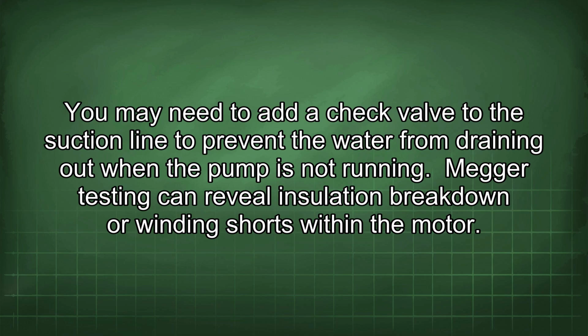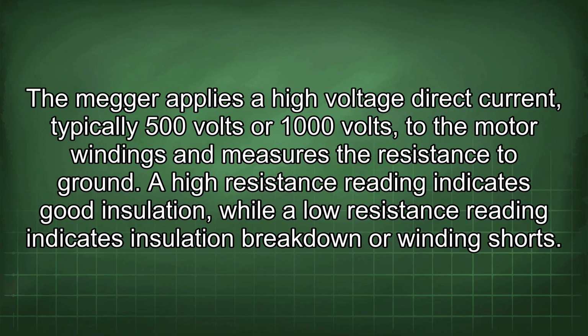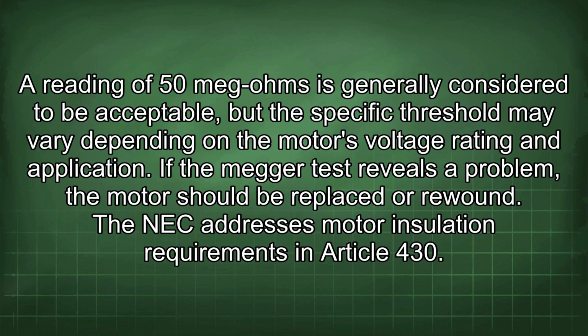Megger testing can reveal insulation breakdown or winding shorts within the motor. The megger applies a high voltage direct current, typically 500 volts or 1000 volts, to the motor windings and measures the resistance to ground. A high resistance reading indicates good insulation, while a low resistance reading indicates insulation breakdown or winding shorts. A reading of 50 megohms is generally considered to be acceptable, but the specific threshold may vary depending on the motor's voltage rating and application. If the megger test reveals a problem, the motor should be replaced or rewound. The NEC addresses motor insulation requirements in Article 430.